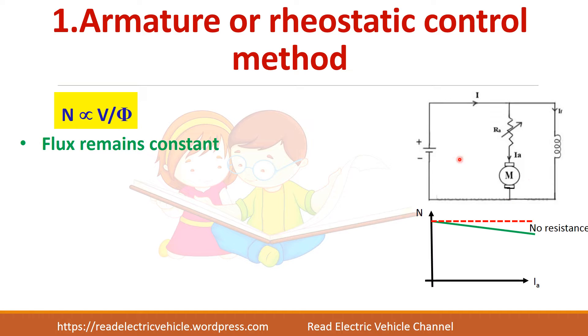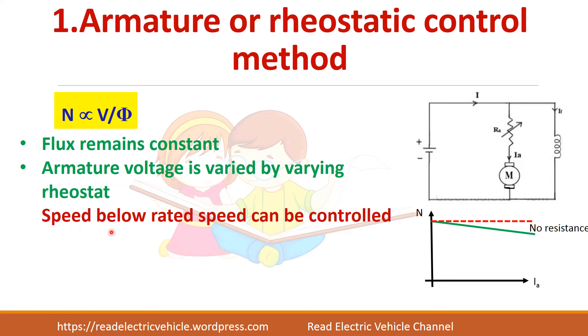You see the diagram here. This is the applied voltage — the total or supply voltage — which remains constant. What we are doing is connecting a resistance in series with the armature. If you increase the drop here, the voltage applied to the armature will reduce. This voltage is fixed; only the drop we are able to change. So in this method we can only reduce the voltage applied to the armature. We cannot increase it, so we can achieve speed control below rated speed only.